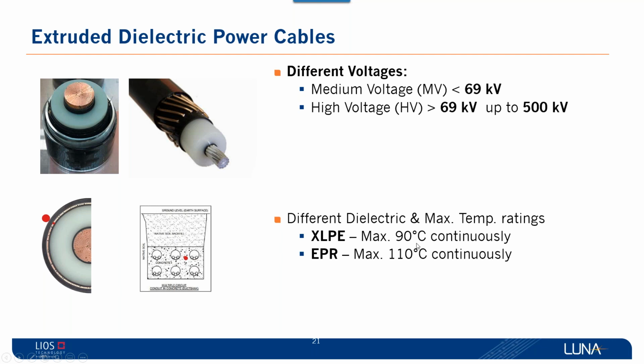For XLPE cables it is 90 degrees Celsius for continuous operation, and for EPR 110. Both can go higher for emergency, and we can talk about that later. The installation over the years has always been that a high voltage cable can have the fiber optic embedded, or it can be outside. And for a distribution line, it can be in a duct bank, in an adjacent conduit next to the distribution network.